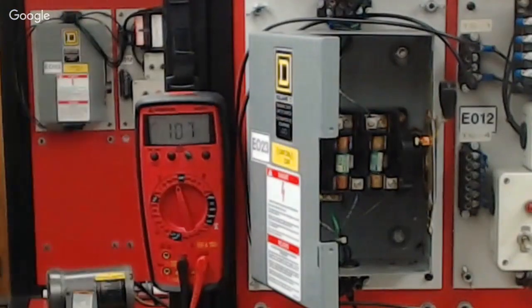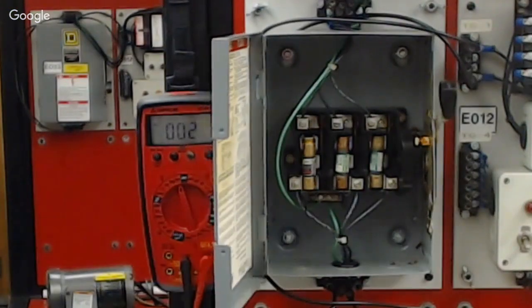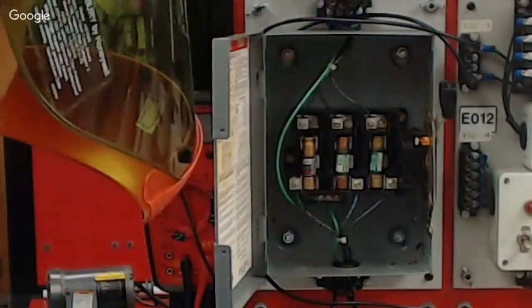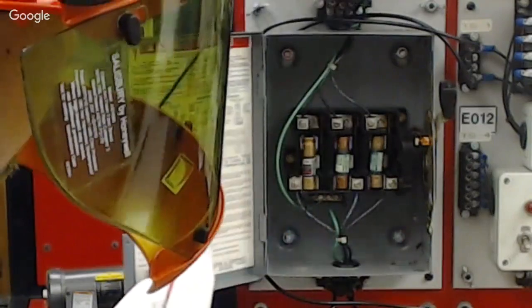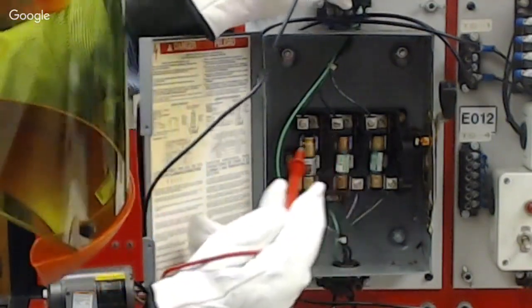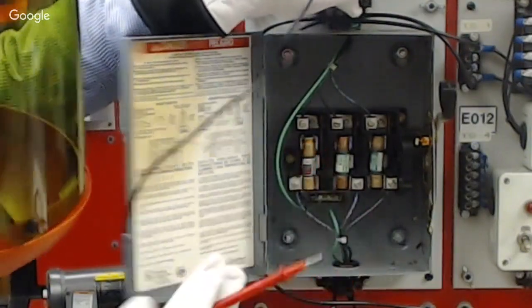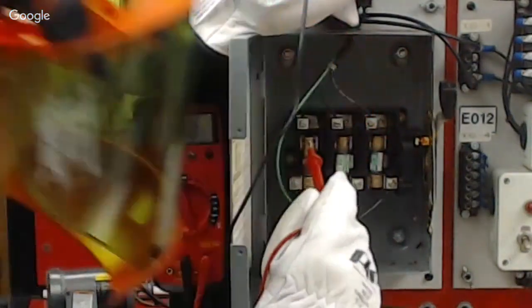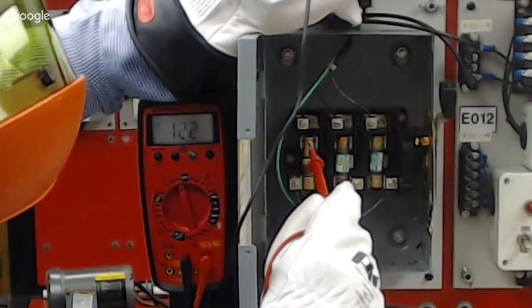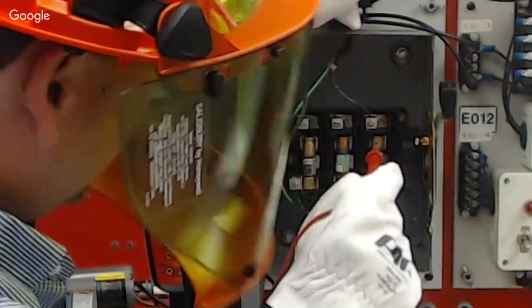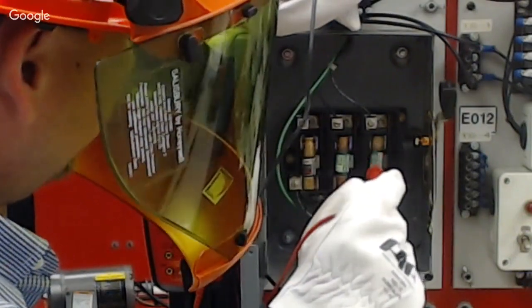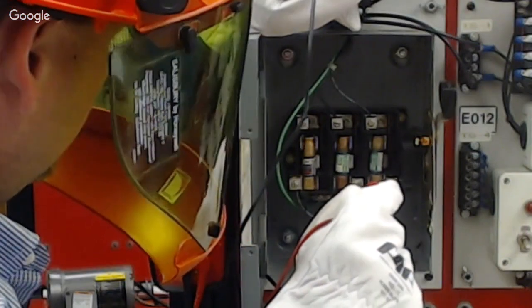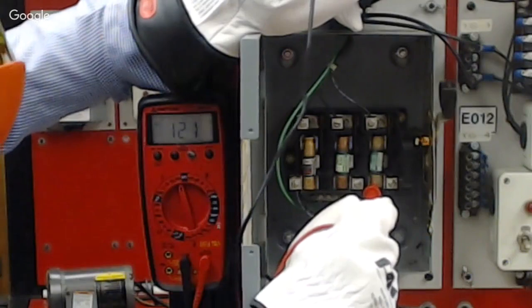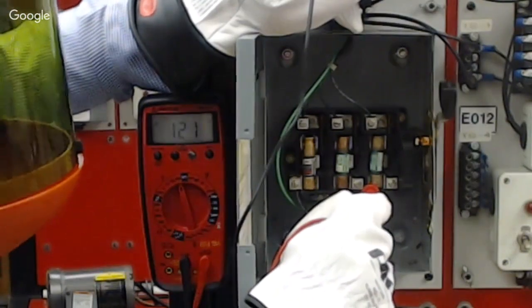I have a control transformer in the circuit. I'm going to come over here and put this back on the voltage. And I'm going to find a ground up here. So I have a ground wire. I'm going to check the ground, and I'm going to check across the top of each one. Here, I'm reading 120 volts to ground. Here I'm reading 120 volts to ground. Remember, this fuse is bad, so what am I reading here? I'm still reading 120 volts to ground, but that fuse I know is bad because I just pulled it out, tested it, and put it back in.